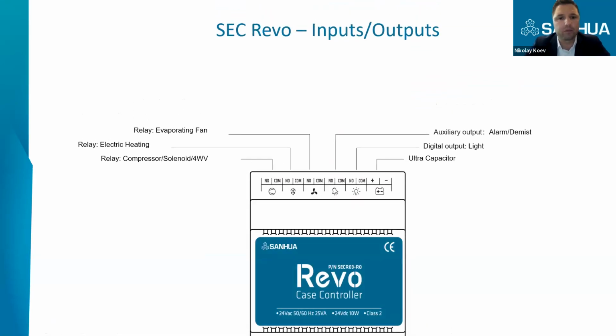And on the top, we have output relays to control the compressor or solenoid valve, electrical defrost, evaporator fans, alarms, and lighting, for example in the cabinet, and the possibility also to connect the supercapacitor. Here it is not integrated. We have a separate device which can be connected to the Revo case controller.